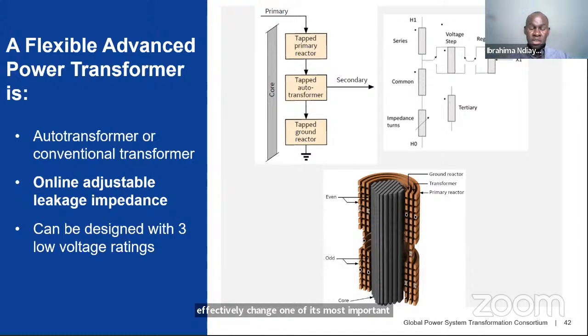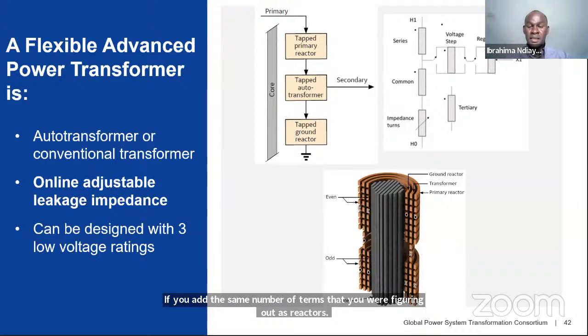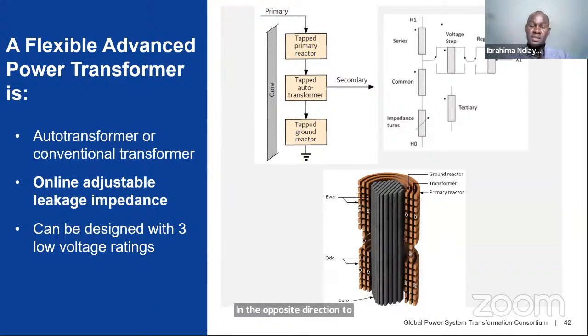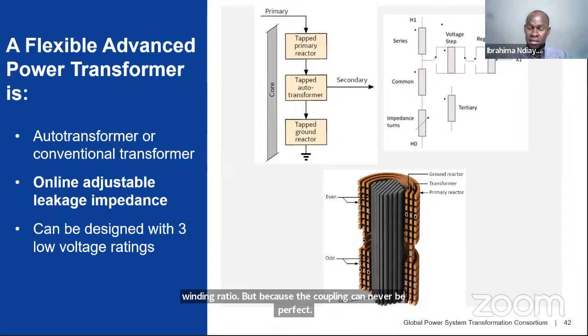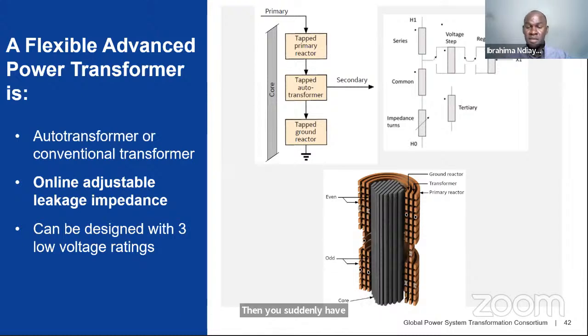To avoid changing the voltage ratio of the transformer, if you add the same number of turns you figured for the reactors in the opposite direction, to cancel the exact magnetic flux added—the number of ampere turns—then you negate that additional reactor effect on the winding ratio. But because the coupling can never be perfect, you suddenly have access to additional leakage impedance.